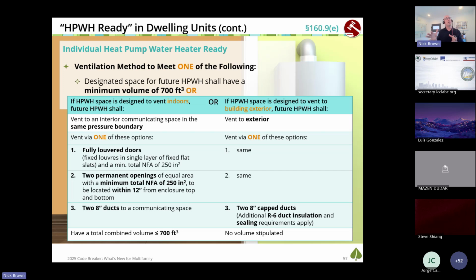And that location we're setting aside for that future heat pump water heater also needs to think along the lines of those air supply requirements we just covered. Have fully louvered doors or high and low grills, or have two 8-inch cap ducts for future ducting of that location.